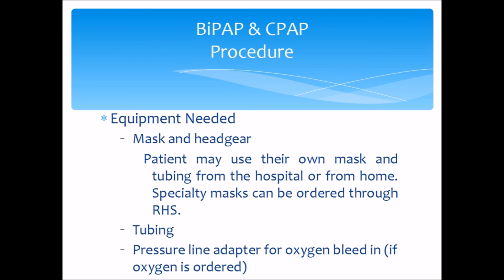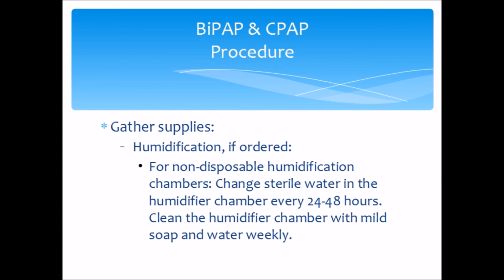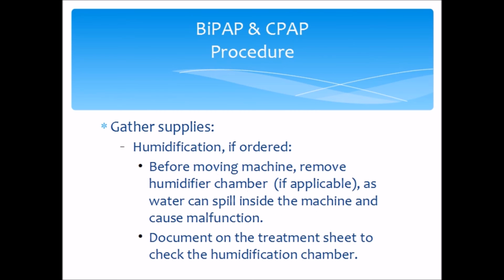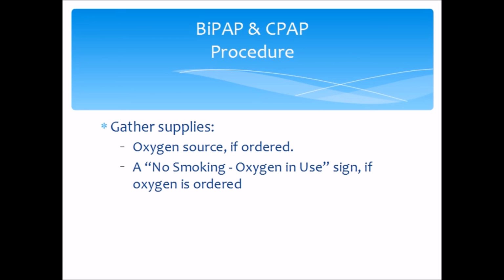Tubing. Pressure line adapter for oxygen bleed-in. Humidification, if ordered. For non-disposable humidification chambers, change sterile water in the humidifier chamber every 24 to 48 hours. Clean the humidifier chamber with mild soap and water weekly. Before moving the machine, remove the humidifier chamber, as water can spill inside the machine and cause malfunction. Document on the treatment sheet to check the humidification chamber. Oxygen source, if ordered. A no smoking oxygen in use sign if oxygen is ordered.